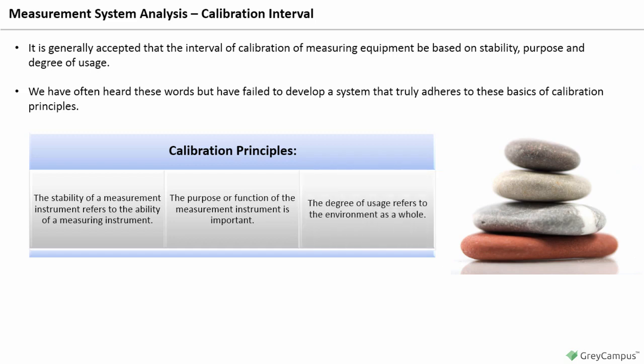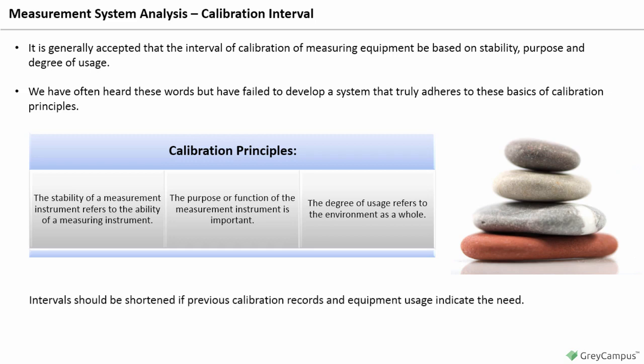The degree of usage refers to the environment as a whole. Thought must be given as to how often an instrument is utilized and to what environmental conditions an instrument is exposed. Contamination, heat, abuse, etc. are all valid considerations. Intervals should be shortened if previous calibration records and equipment usage indicate this need. The interval can be lengthened if the results of prior calibrations show that accuracy will not be sacrificed. Intervals of calibrations are not always stated in standard lengths of time, such as annually, biannually, quarterly, etc.